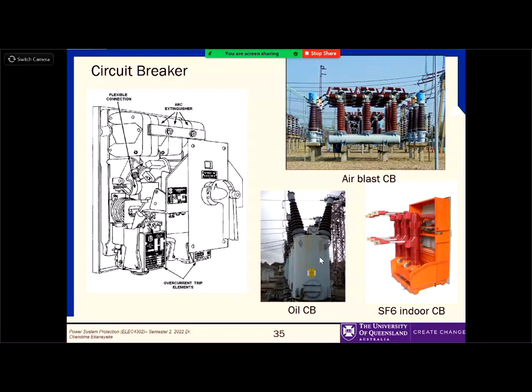It produces a lot of arcs, and then you have to quench that arc. Quench means you have to suppress the arc using different mechanisms. In an air blast circuit breaker, it's just air—they blast air into the arc, but it will be huge because air is not a good insulator or cooler. Oil, however, is a very good cooling mechanism, so it can quench the heat produced by the arc and absorb that heat.